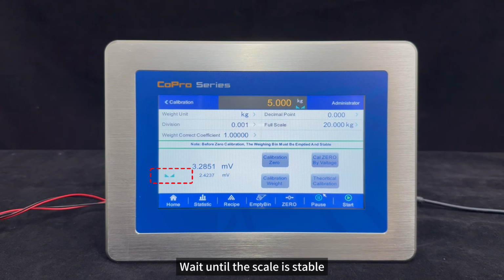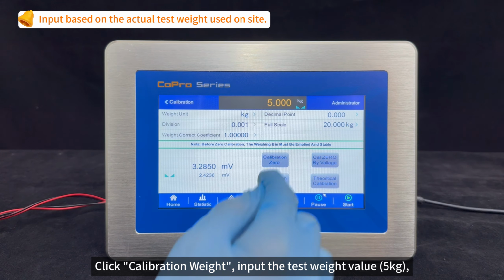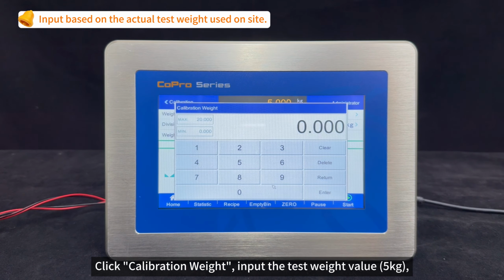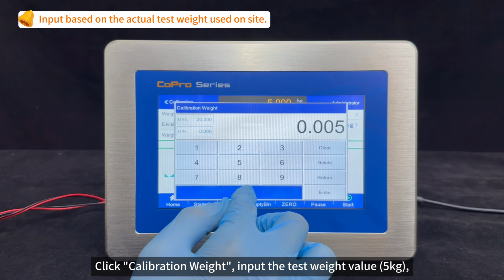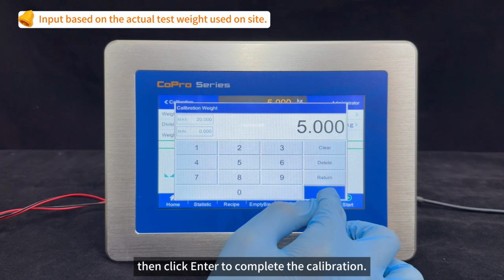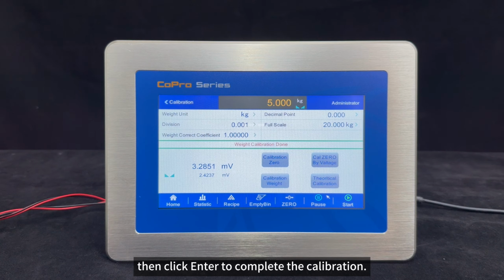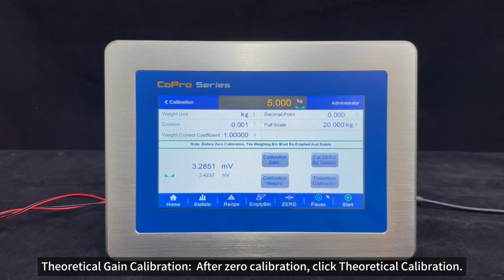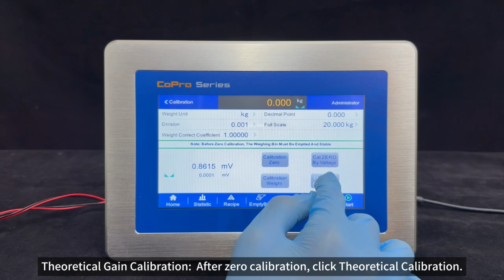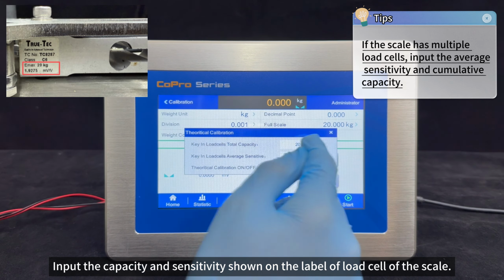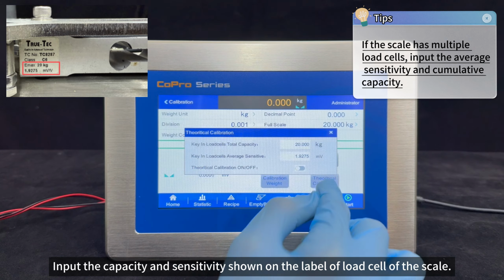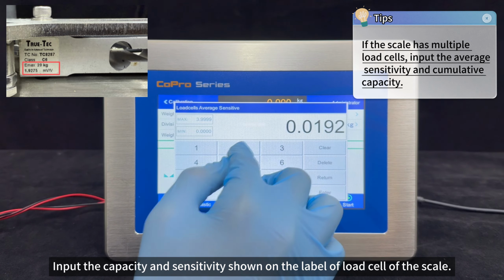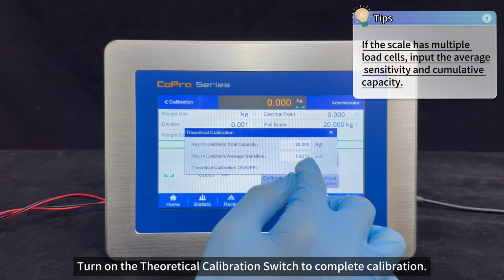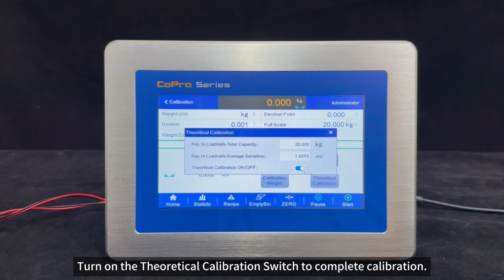Wait until the scale is stable. Click Calibration Weight. Input the test weight value 5 kilograms. Then click Enter to complete the calibration. Theoretical gain calibration. After zero calibration, click Theoretical calibration. Input the capacity and sensitivity shown on the label of load cell of the scale. Turn on the theoretical calibration switch to complete calibration.